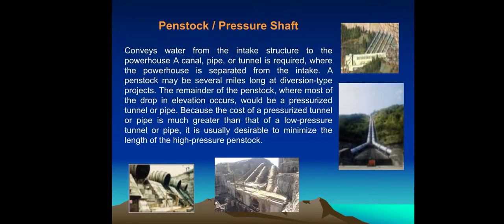Penstock pressure shafts convey the water from the intake structure to the powerhouse. A canal, pipe, or tunnel is required where the powerhouse is separated from the intake. A penstock may be several miles long at a diversion-type project. The remainder of the penstock, where most of the pressure drop occurs, would be a pressurized tunnel or pipe. Because the cost of a pressurized tunnel or pipe is much greater than that of a lower-pressure tunnel or pipe, it is usually desirable to minimize the length of the high-pressure penstock.